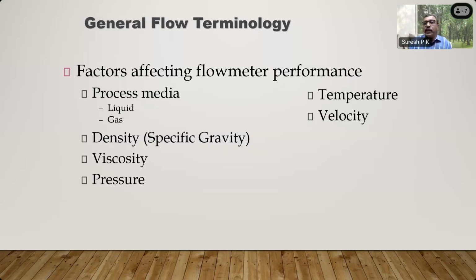So these things can affect your measurement. Therefore, the flow meter manufacturer is the best person to select a flow meter from his range of products for your application. It's not you who can select a particular one. Of course, if you have a history of a particular flow meter which is performing properly in a particular application, then you can buy the same flow meter.